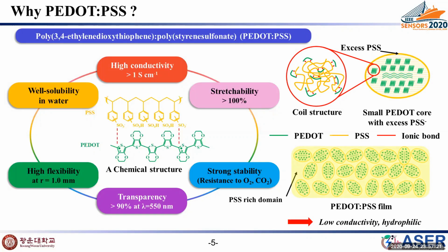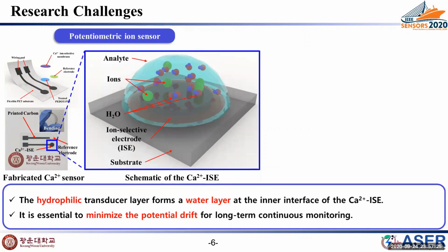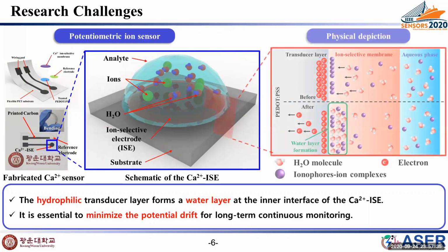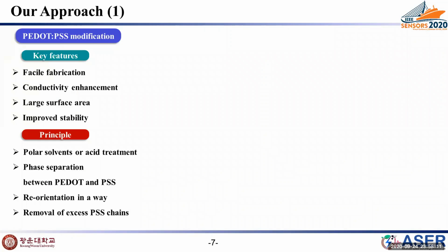As you can see, the potentiometric ion sensor consists of a reference electrode and an ISE, including a transducer layer and an ion selective membrane. When the sensor's ISE contacts the analyte, water molecules and target ions can pass through the ion selective membrane. At this time, the higher the hydrophilic properties of the transducer layer, the more easily water molecules are pushed to form a large water layer. And this aqueous layer causes a potential drift over time. Therefore, reducing the hydrophilic properties of the solid contact material is a way to be stable. And it is our approach.